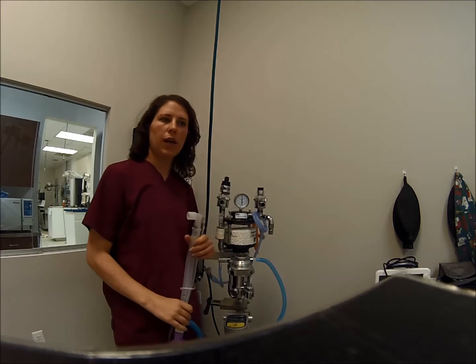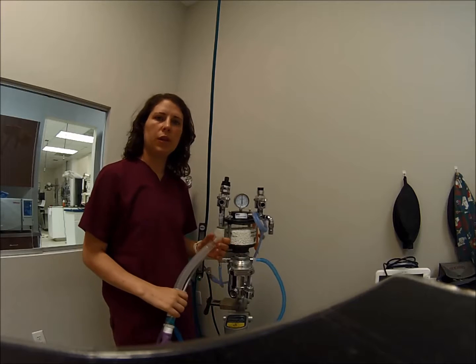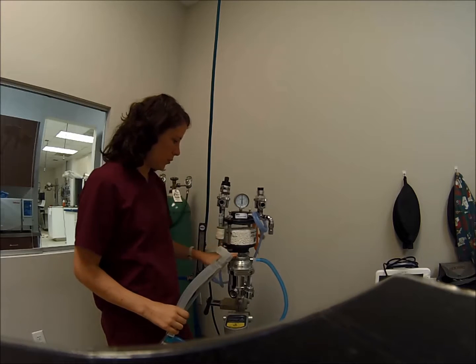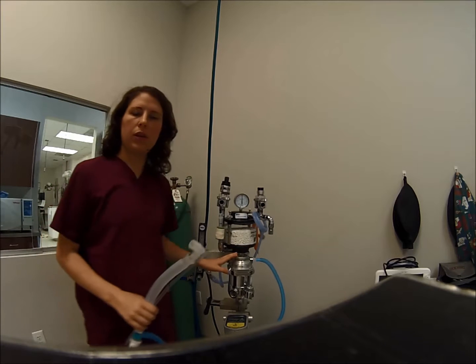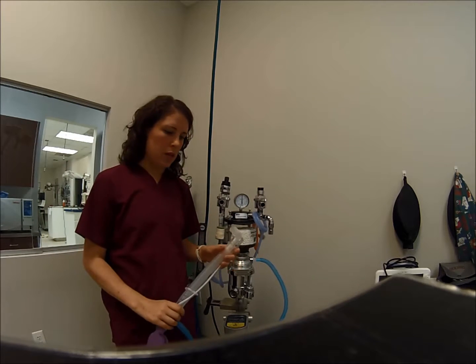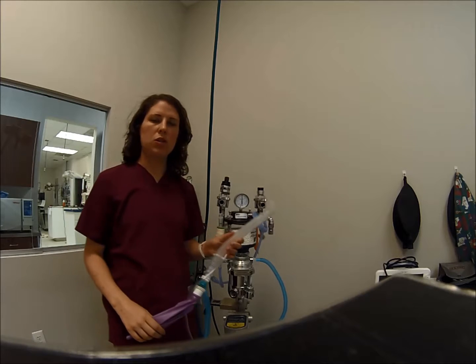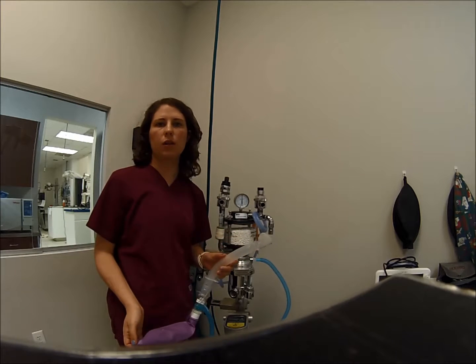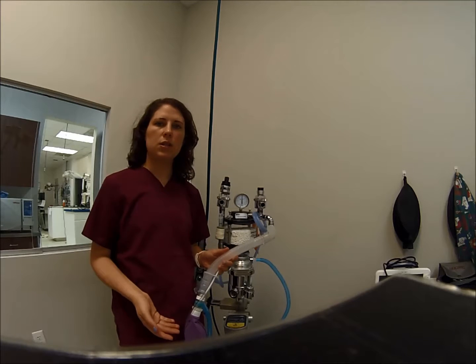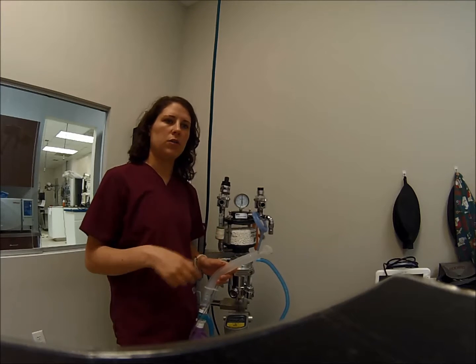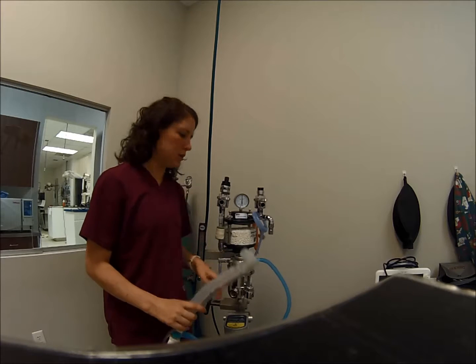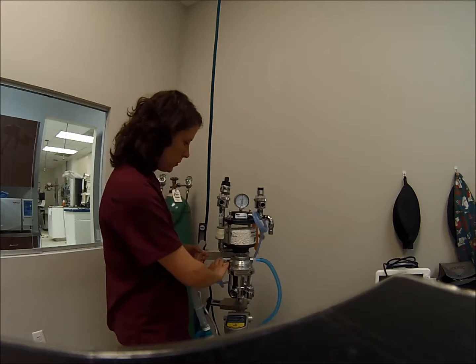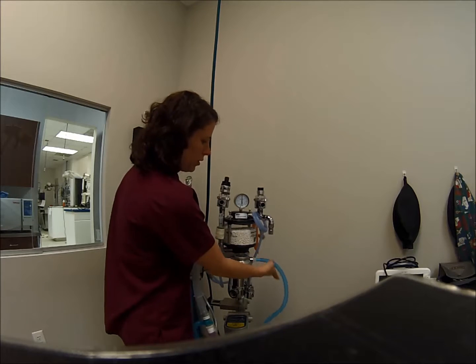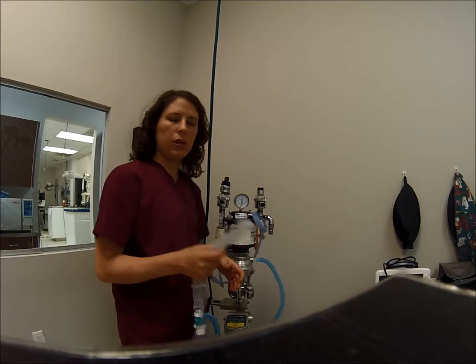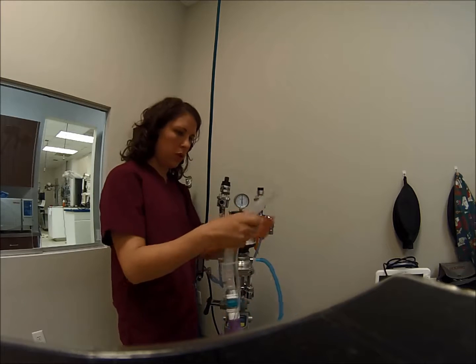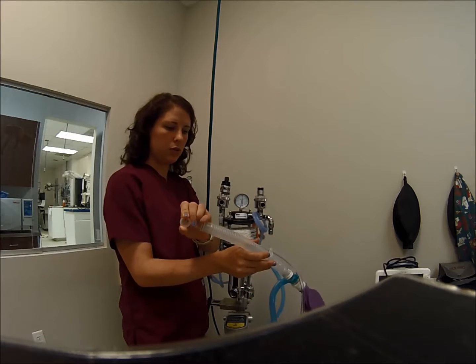In the previous video, I had hooked up the rebreathing circuit, but in this portion I have my non-rebreathing tubing hooked up. This is a good circuit that can be used for patients that are small and weighing less than 7 kilograms because there's low gas resistance, but you do need a higher oxygen flow rate to deliver the anesthetic. So I have my oxygen hooked up to the vaporizer, and then on my outlet port is my non-rebreathing tubing, which will have this end hooked up to the endotracheal tube.